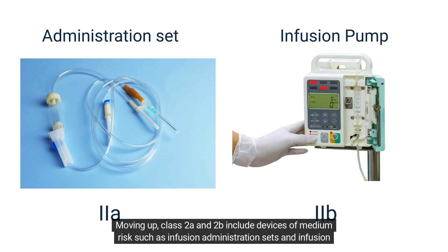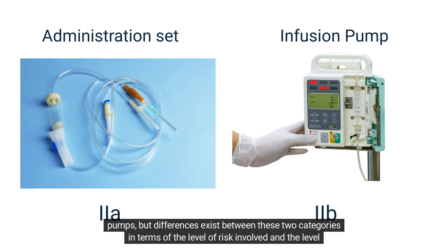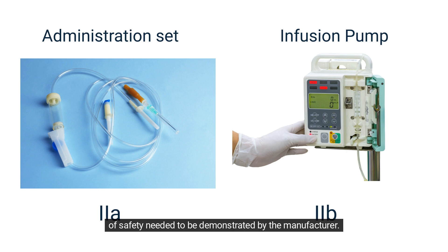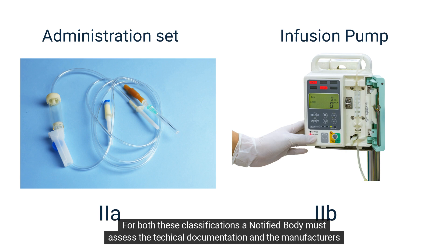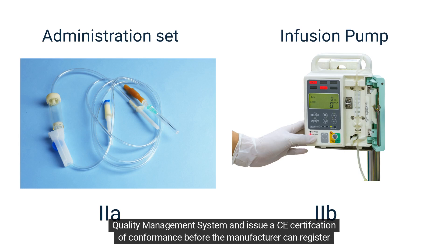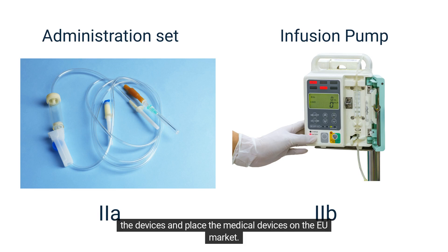Moving up, class 2A and 2B include devices of medium risk such as infusion administration sets and infusion pumps, but differences exist between these two categories in terms of the level of risk involved and the level of safety needed to be demonstrated by the manufacturer. For both classifications, a notified body must assess the technical documentation and the manufacturer's quality management system and issue a CE certification of conformance before the manufacturer can register the devices and place them on the EU market.